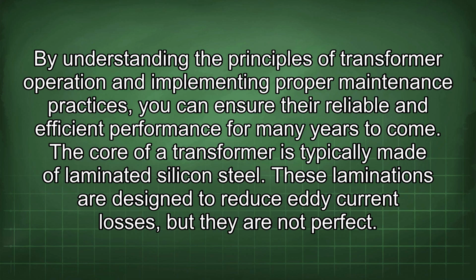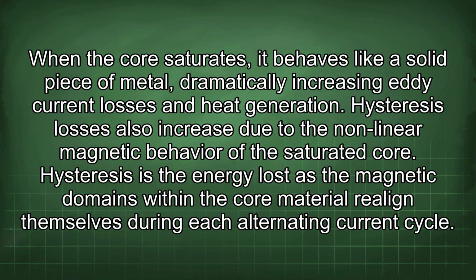The core of a transformer is typically made of laminated silicon steel. These laminations are designed to reduce eddy current losses, but they are not perfect. When the core saturates, it behaves like a solid piece of metal, dramatically increasing eddy current losses and heat generation. Hysteresis loss is also increased due to the nonlinear magnetic behavior of the saturated core.